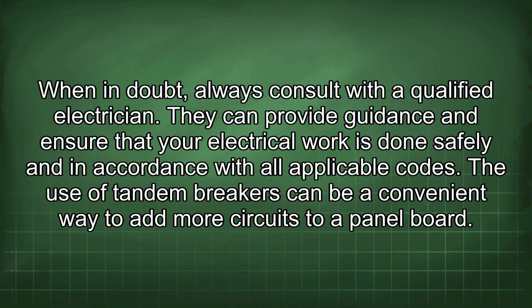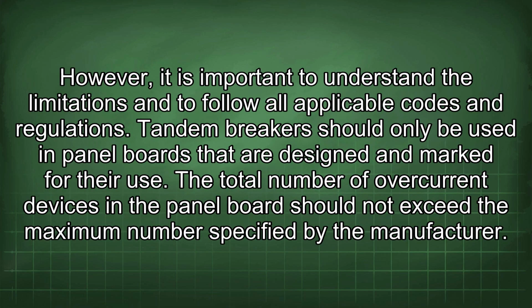The use of tandem breakers can be a convenient way to add more circuits to a panel board. However, it is important to understand the limitations and to follow all applicable codes and regulations. Tandem breakers should only be used in panel boards that are designed and marked for their use. The total number of overcurrent devices in the panel board should not exceed the maximum number specified by the manufacturer.